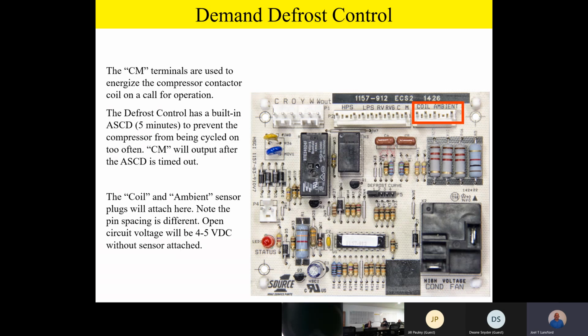Another little side note: if you remove the sensor from the board, you can always take your voltmeter and check the voltage on those pins. The voltage on the pins should be about 4 to 5 volts DC without anything plugged on. So if I remove a sensor, that's actually a pretty important check. You remove the sensor and check the voltage on those pins. It should be 4 to 5 volts DC. Now watch how easy it is to troubleshoot this board. If I have 24 volts on the board between R and C that we talked about earlier, common and 24 volt hot, and I unplug the sensors from that board, I should read 4 to 5 volts DC on those pins. If I don't, you don't have to go any further. It's a bad board. The DC power supply has failed, and the board's bad.